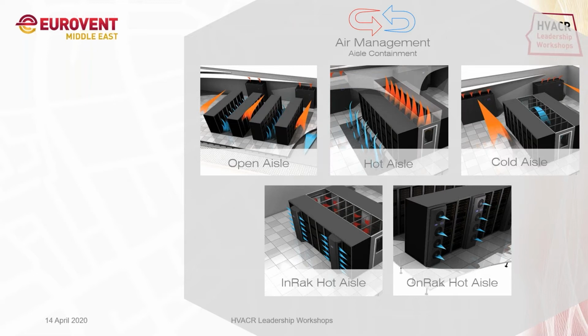So I was talking about the aisle containment or air management. We have open aisle architecture where there is a mixing of air with the room temperature or room air, and we have the hot aisle where the hot air is contained. We have the cold aisle where the cold air is contained. These all are the arrangement of the server racks back to back or front to front. Then we have the in-rack hot aisle, which are server in-rack coolings. For the on-rack, it's like a backdoor cooling.